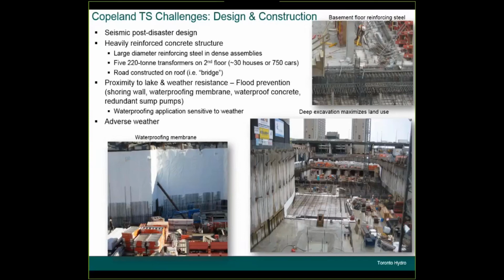The other aspect is that under the Ontario Building Code, we had to ensure that we had seismic post-disaster design. That entailed a heavily reinforced concrete structure. We had large diameter reinforcing steel in very dense assemblies. So we had a transformer slab that was 500 millimeters thick, that would support the 5 transformers in the final configuration of the transformer station. There will be 5 gas-insulated transformers, and each of them weigh, with their associated equipment, 220 tons. So a 500 millimeter thick reinforced concrete floor, under which there is a cable basement, and then a mat slab foundation that is approximately 6 feet thick.